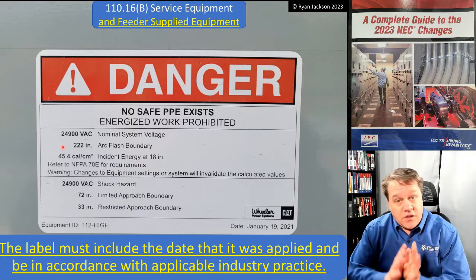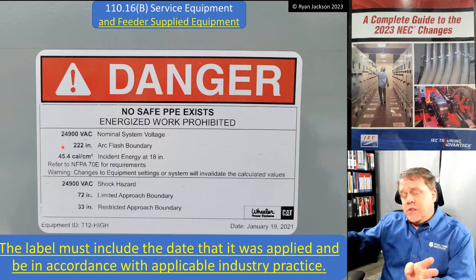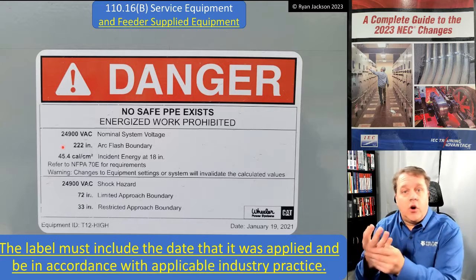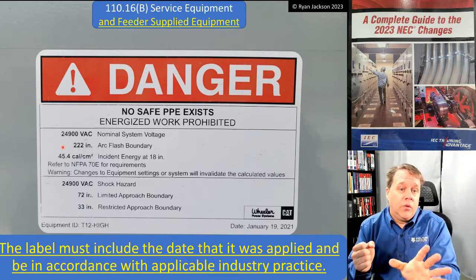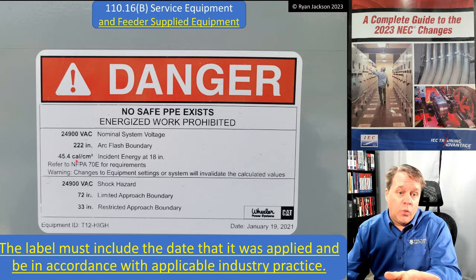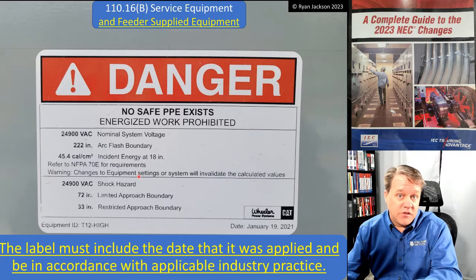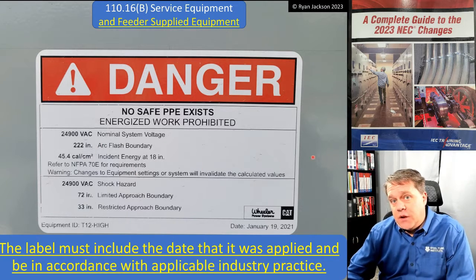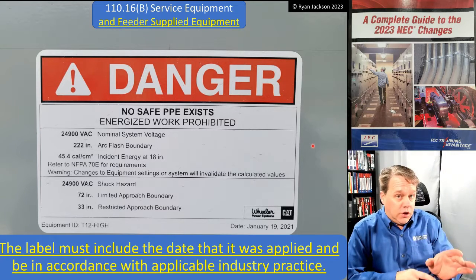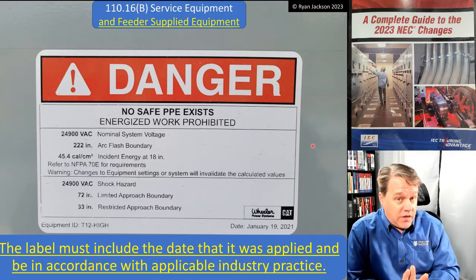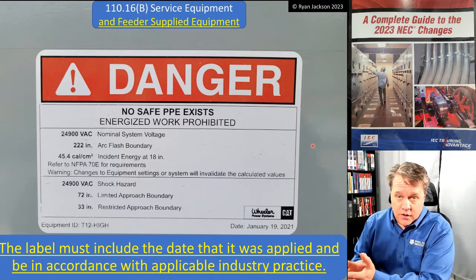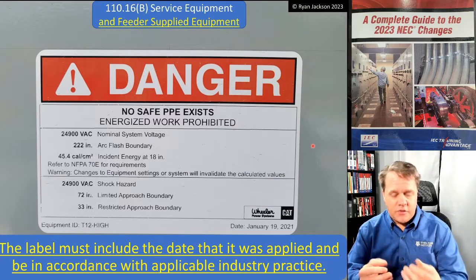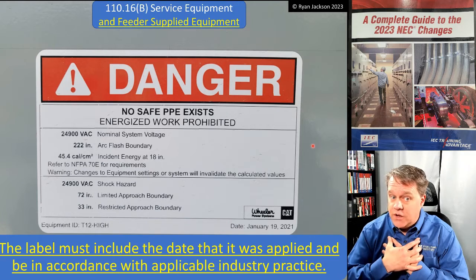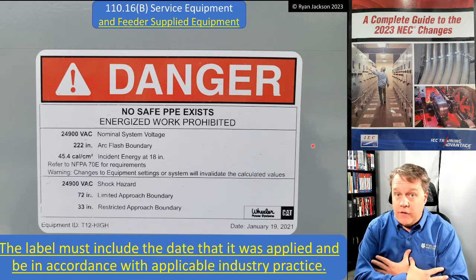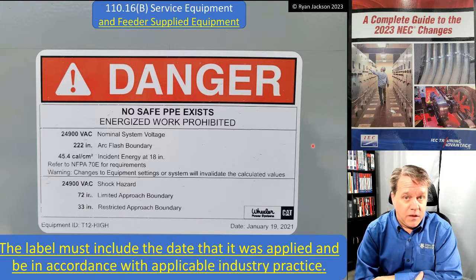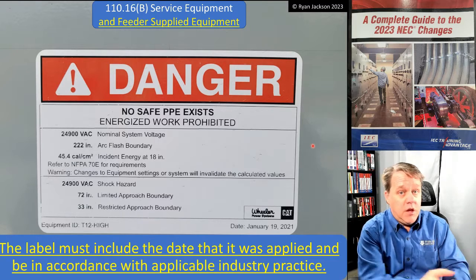Arc flash boundary is what? That's the distance from the source of the arc that you need to be in order to avoid second degree burns on exposed skin. Okay, so in other words, if you're naked in front of this equipment, within 222 inches of it, and it flashes, you're going to get a second degree burn. Now, I say naked because of this. You're either wearing fuel or you're wearing PPE, right? Wearing nothing is better than wearing the wrong thing. Look, love this shirt. This shirt is comfy and it's from my steel tube guys. I would not want to be wearing this in an arc flash, because I better love this shirt, because I'm going to be wearing it the rest of my life if I'm in an arc flash and it happens, because it's going to melt into my flesh. All right? You need to have PPE on, because if you're not wearing PPE, you're wearing fuel.